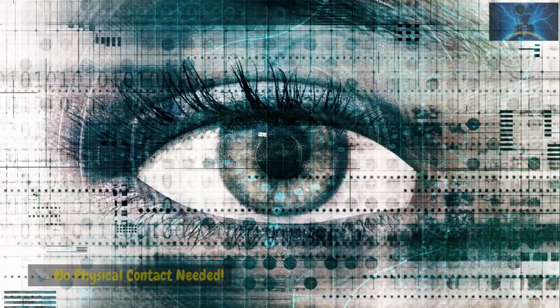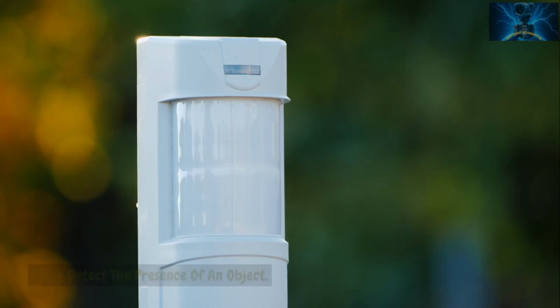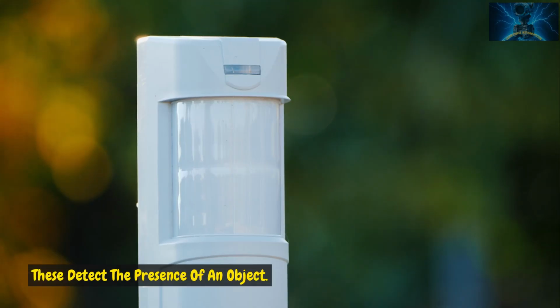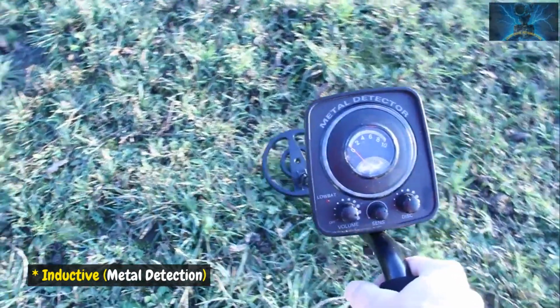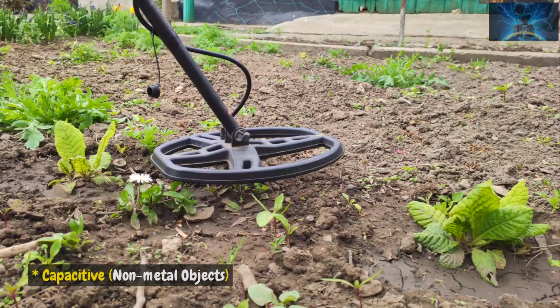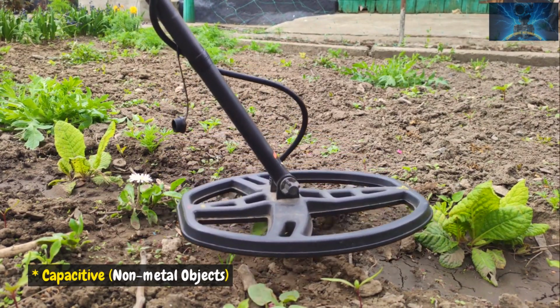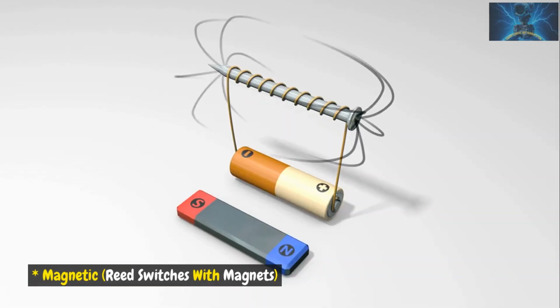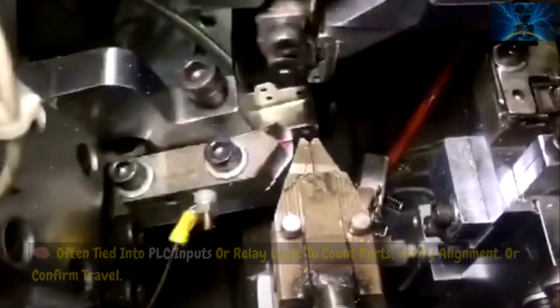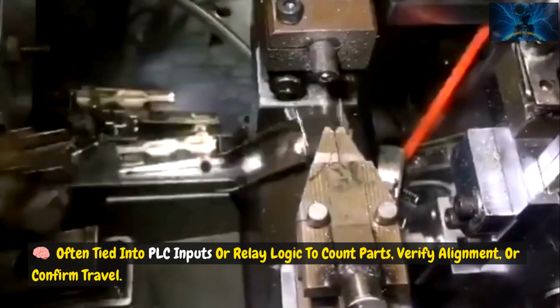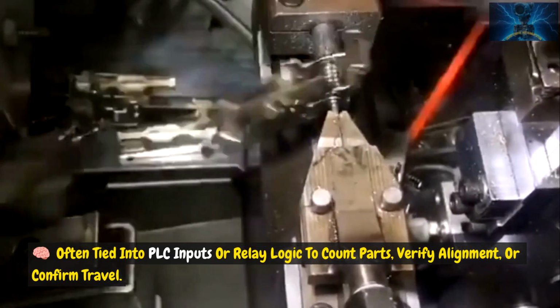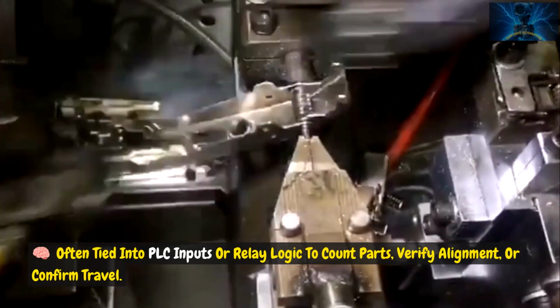Proximity switches. No physical contact needed. These detect the presence of an object. Common types: inductive, metal detection. Capacitive, non-metal objects. Magnetic, reed switches with magnets. Often tied into PLC inputs or relay logic to count parts, verify alignment, or confirm travel.